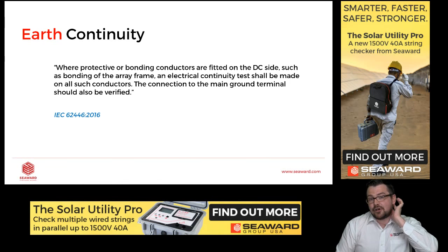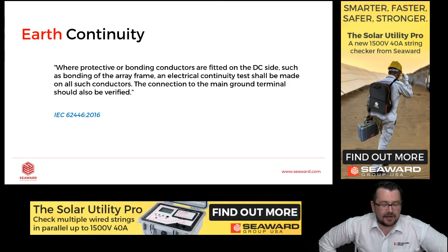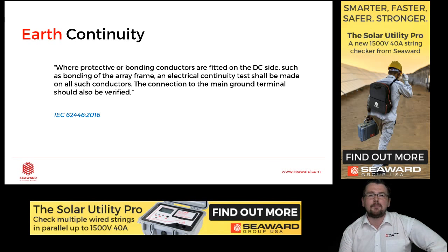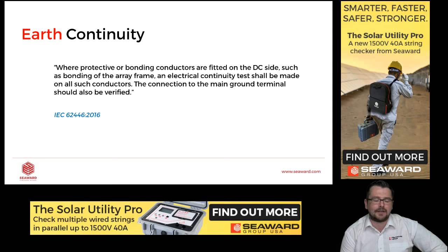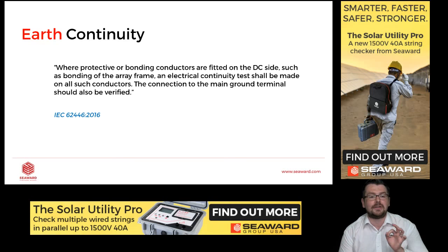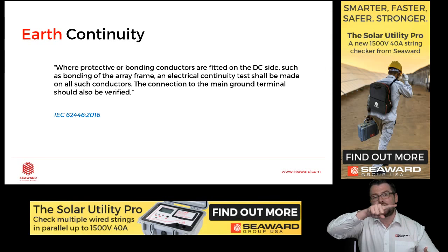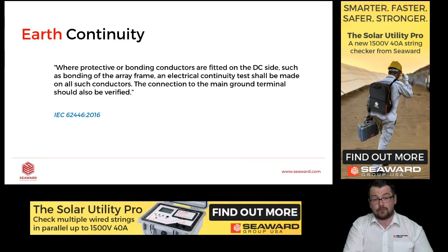So first of all, we have earth continuity, and this is a very standard electrical test, particularly in portable appliance testing and in the residential sector of electronics. So where the protective or bonding conductors are fitted on the DC side, such as the bonding of the array frame, an electrical continuity test shall be made on all of those conductors. The connection to the main ground terminal should also be verified. So basically what we're doing is we're ensuring that any leakage current has a path to ground. So no one's going to get a shock. We have a good grounding on the system.